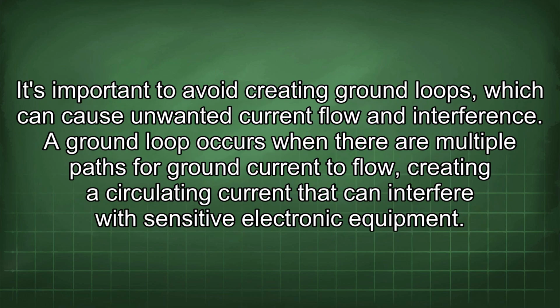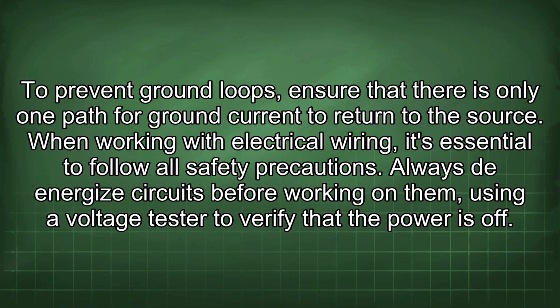It's important to avoid creating ground loops, which can cause unwanted current flow and interference. A ground loop occurs when there are multiple paths for ground current to flow, creating a circulating current that can interfere with sensitive electronic equipment. To prevent ground loops, ensure that there is only one path for ground current to return to the source.